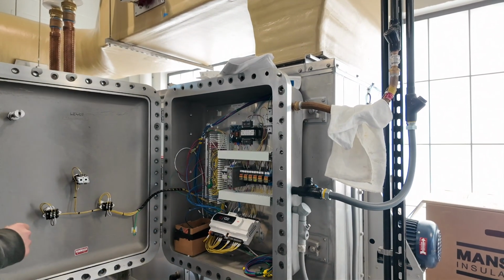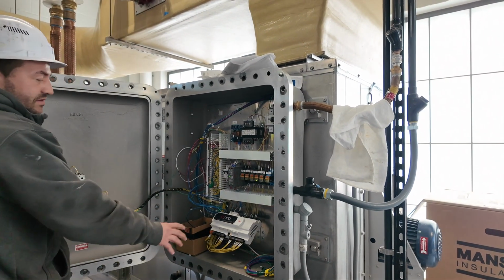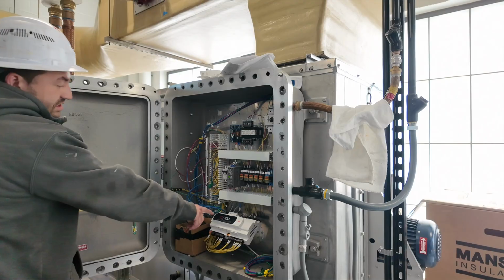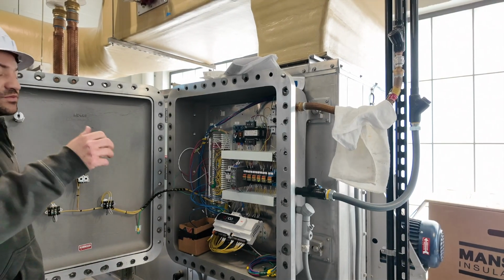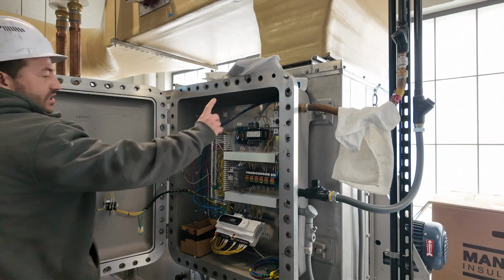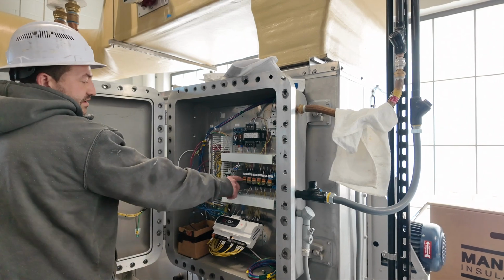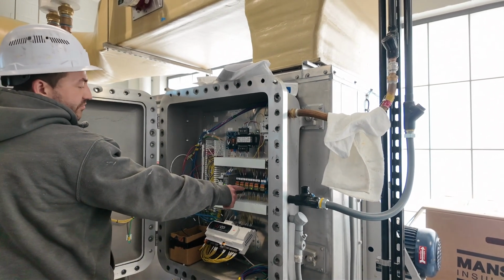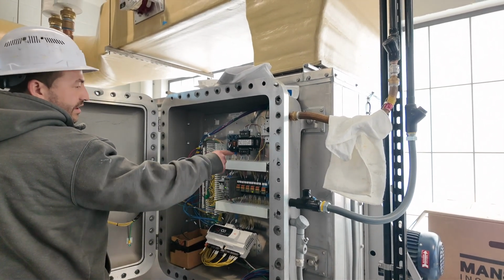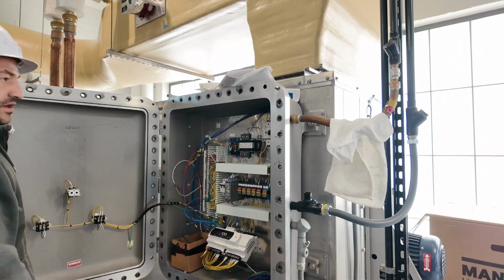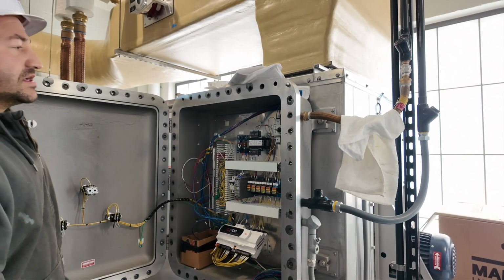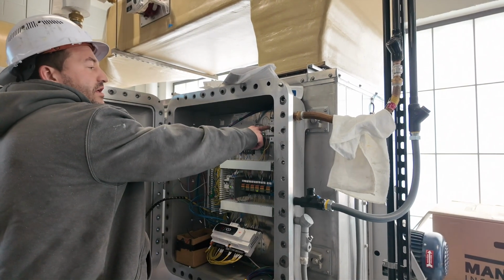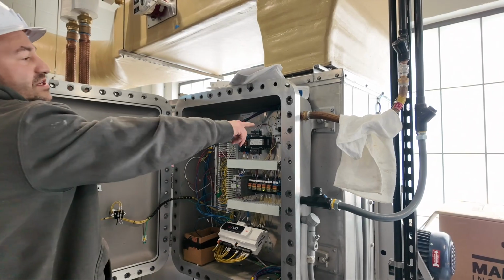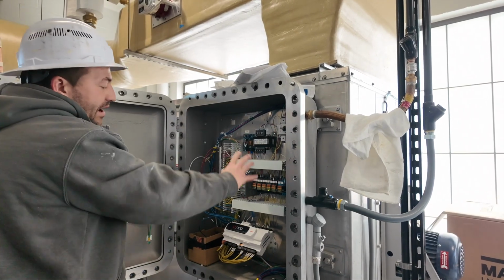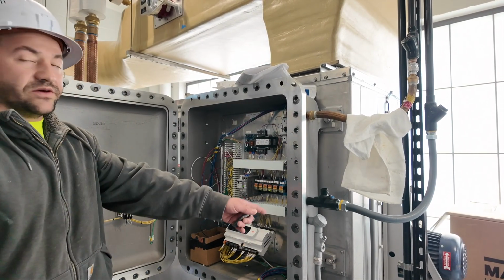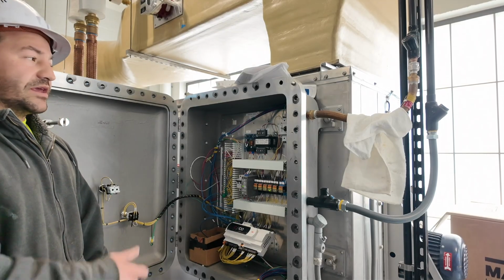Inside the panel here, we'll go to the terminal strip, and this is your actual controller. So this is communicating back to that handheld to display you basically everything that's going on here. You disconnect a couple little circuit breakers here, bank of relays, so whatever relay is lit up, it'll be green. It's a 24-volt transformer there. The power from the VFD is coming in straight to this here. So if you have this breaker off, you'll still have power to the other controls. You're just basically killing the fan motor.